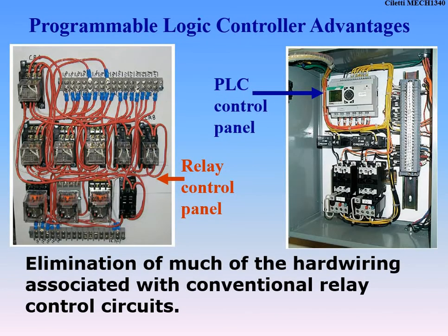I keep talking about relay control. If you look at the image on the left, that's a relay control panel — lots of wiring, lots of different things that can go wrong, and troubleshooting is difficult if a relay goes bad. These are nice because they're clear ones — you can physically look at the relay. But we can update it so that it's a PLC control panel, wired to different IOs that open and close as we automatically tell them to. A lot cleaner of a control panel, and we can do a lot more with PLCs.